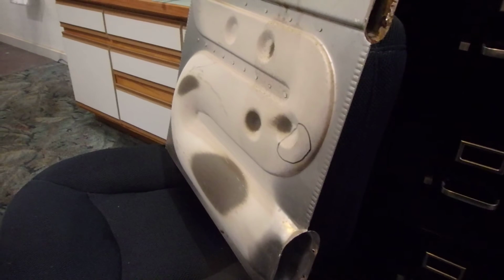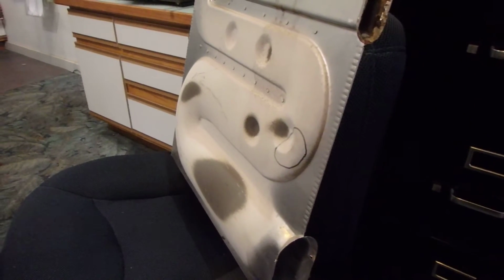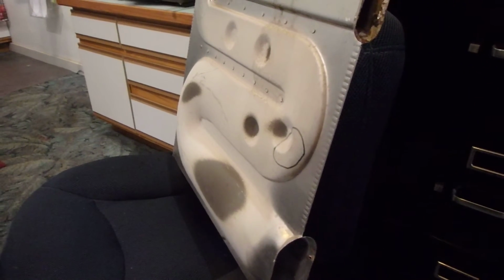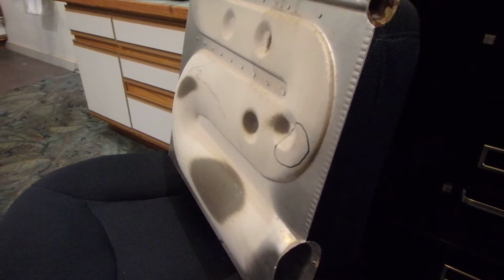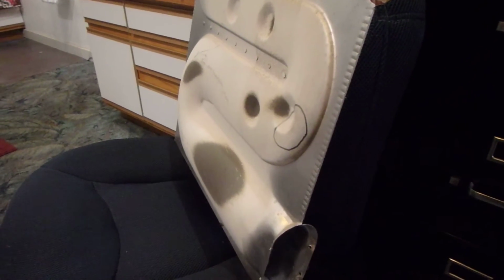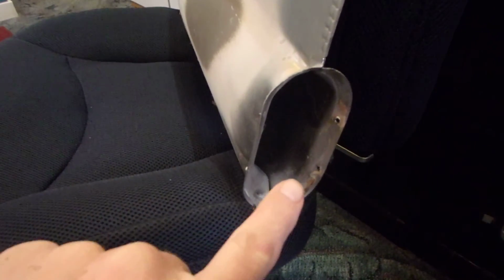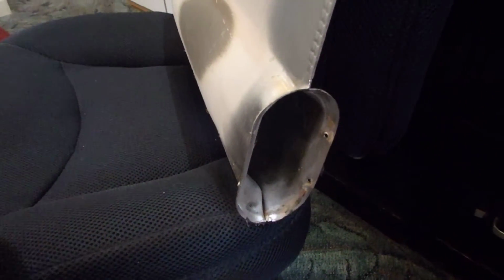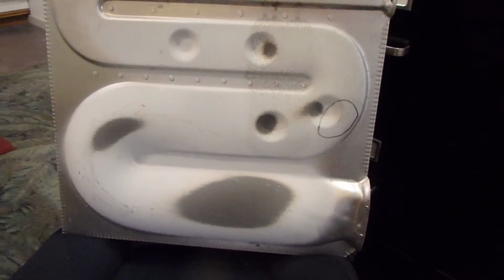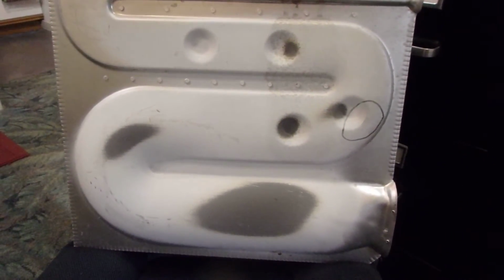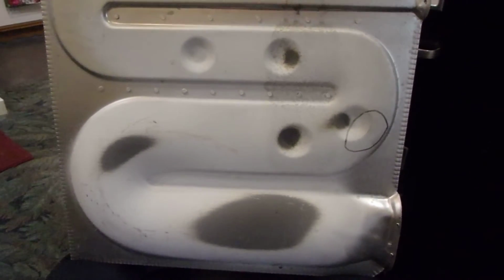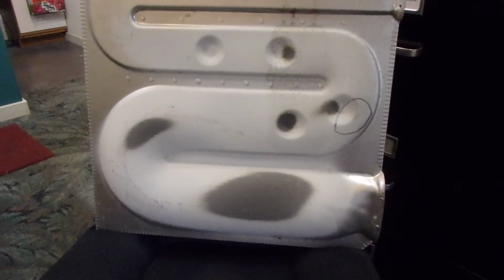And what you're looking at now is a heat exchanger. It's actually one cell. If I had, say, a 60,000 BTU furnace, I'd have three of these side by side. The only part of it I can see during an inspection is right down here, that opening where the flames go. Once the flames get in there—and I'm going to turn this around—they follow this serpentine course, which slows them down so that you can get good transfer of heat to the air being circulated around it.